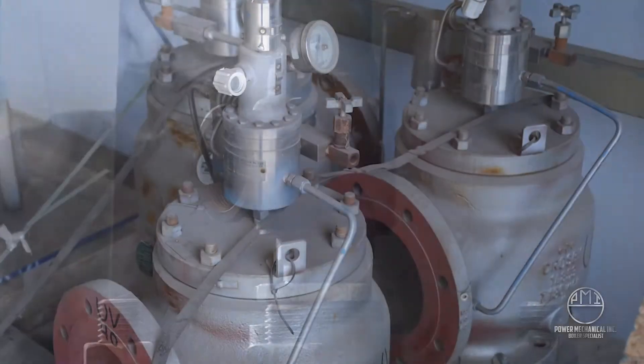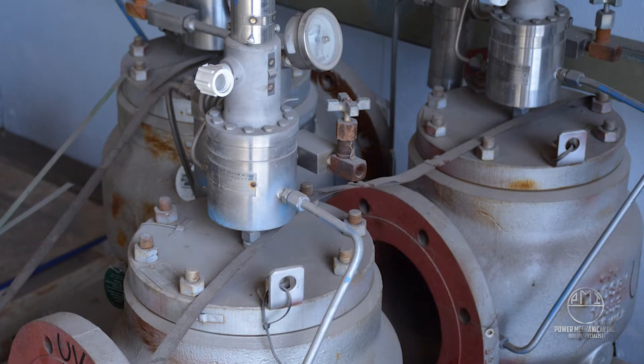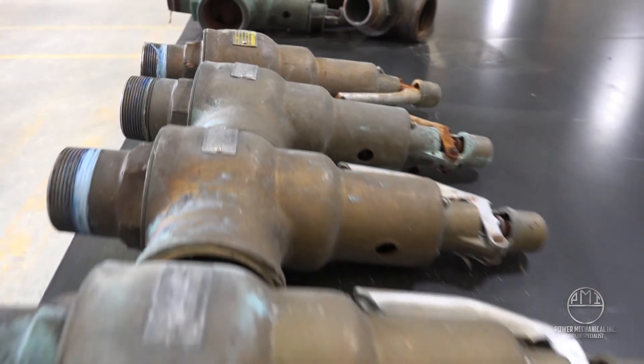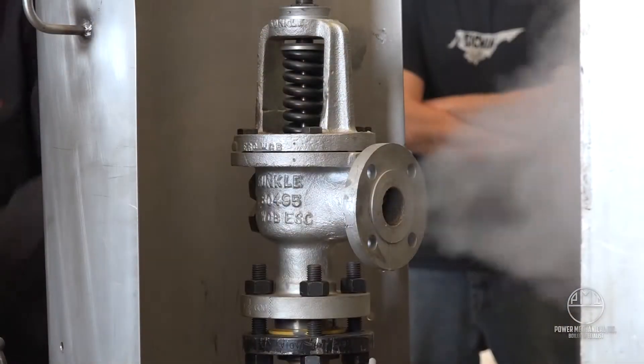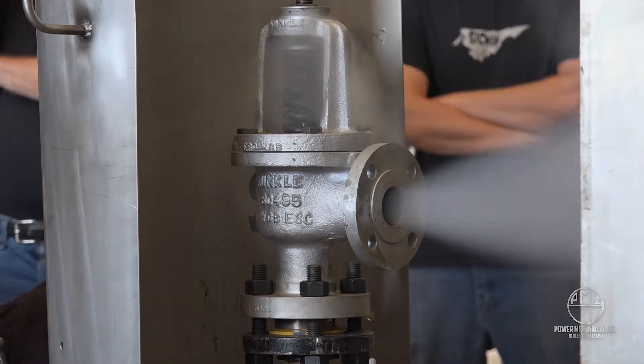Safety valves, also known as relief valves or safety relief valves, have several different designs and specifications. A common type for many steam boiler applications is a spring-loaded safety valve. These valves are set according to the pressure and flow requirements of the vessel to which they are installed.